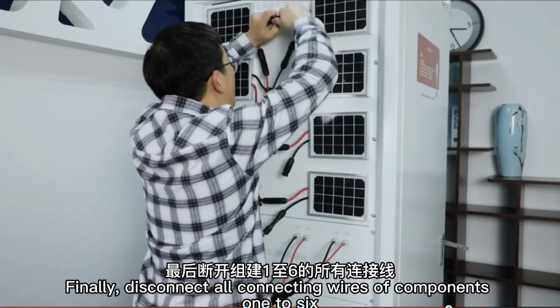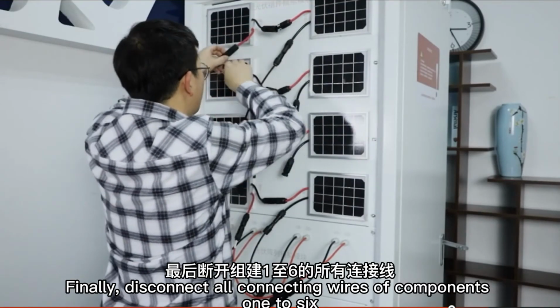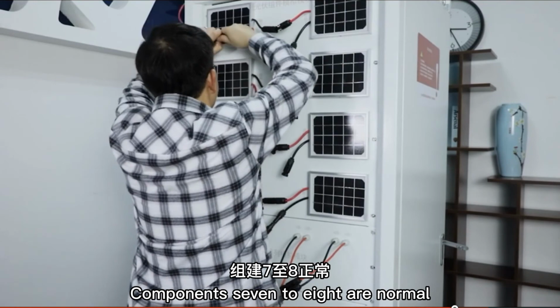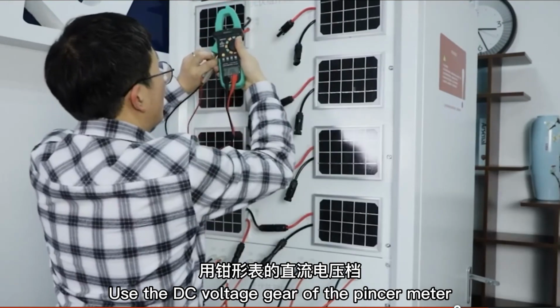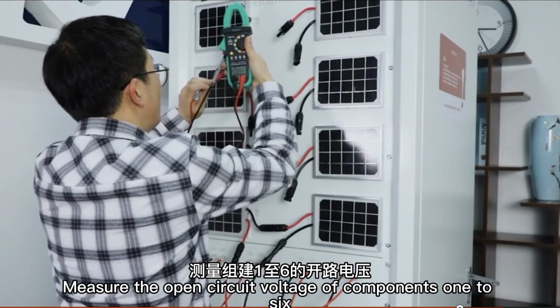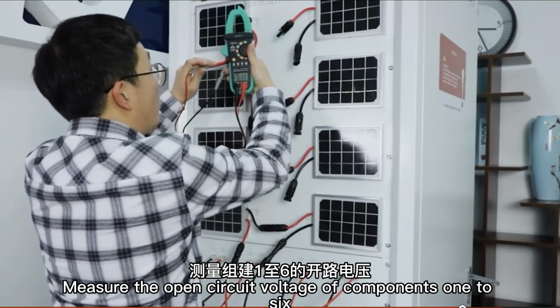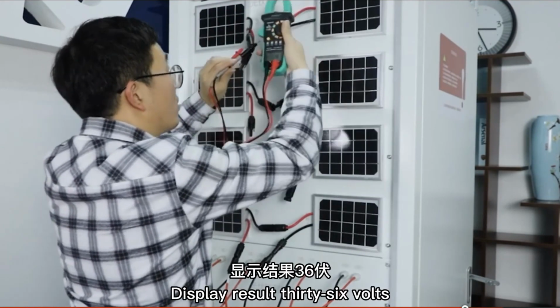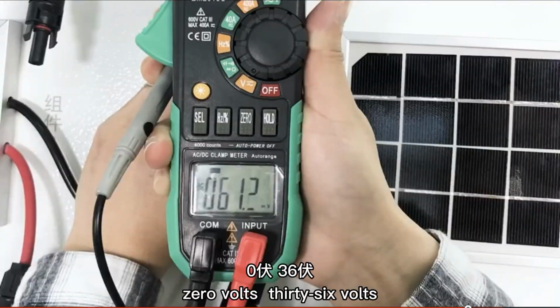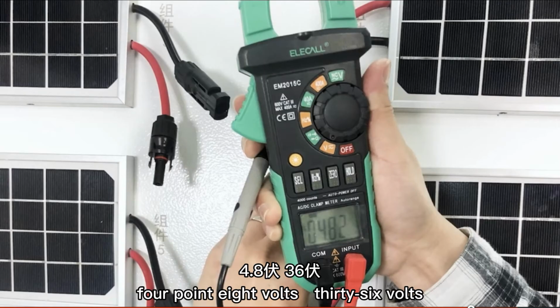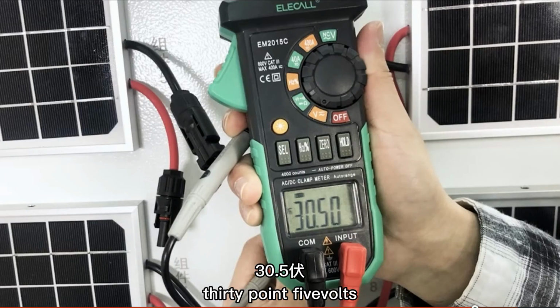Finally, disconnect all connecting wires of components 1 to 6. Components 7 to 8 are normal. Use the DC voltage gear of the clamp meter. Measure the open circuit voltage of components 1 to 6. Display results: 36 volts, 0 volts, 36 volts, 4.8 volts, 36 volts, 30.5 volts.